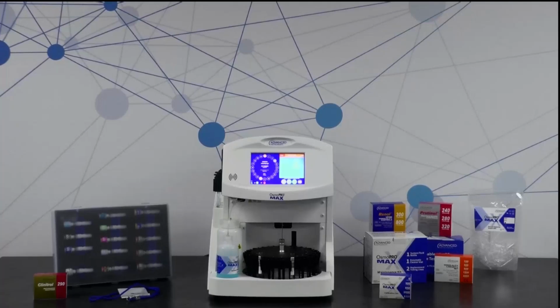We are working on, because this is actually something that's come up a couple times, a software update that will allow you to toggle in the menu the ability to automatically average two results that are within an acceptable range of each other and cross only one result over into the LAS. So if that's something you're interested in, I can definitely keep you up to date on our progress around that. We're thinking maybe a couple months as far as where we're at in the software development queue, but something that's up and coming. Okay. And then will it wait to have the two results within range? Yes. So it's not going to send anything over until it's identified two results that are within range of each other, within the range that you set. So you don't have to worry about it prematurely sending anything over.